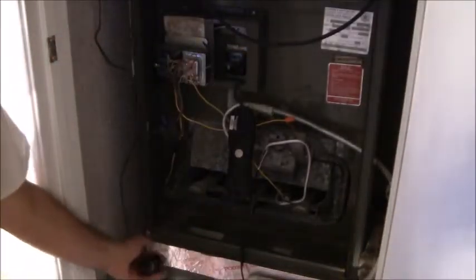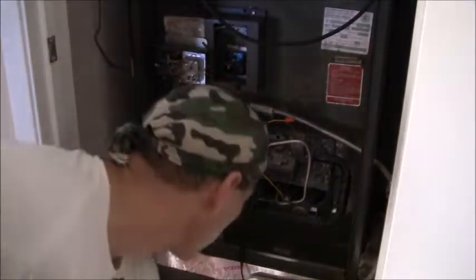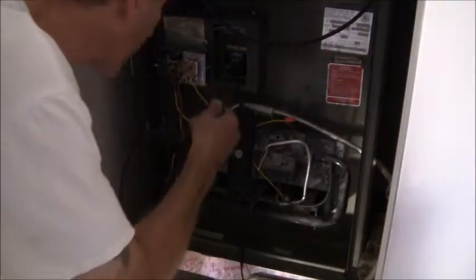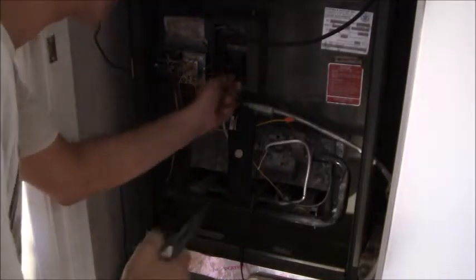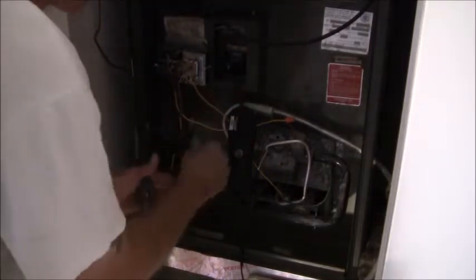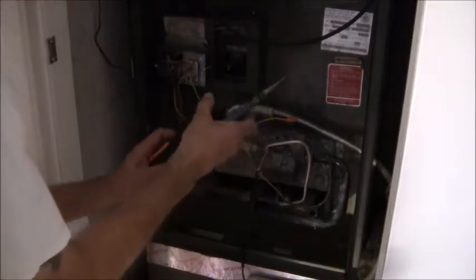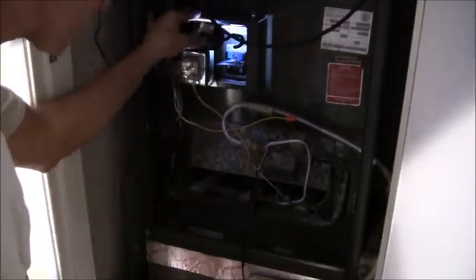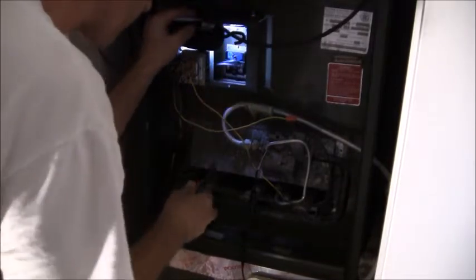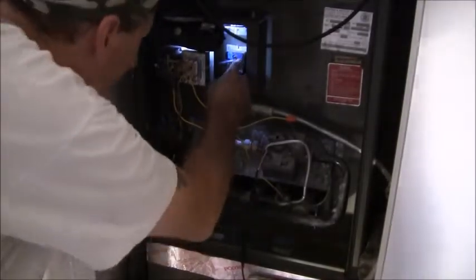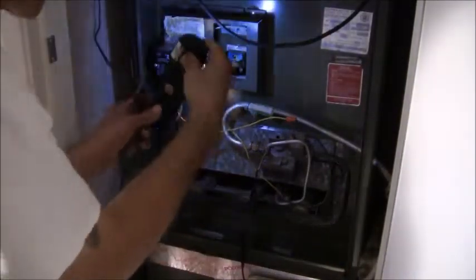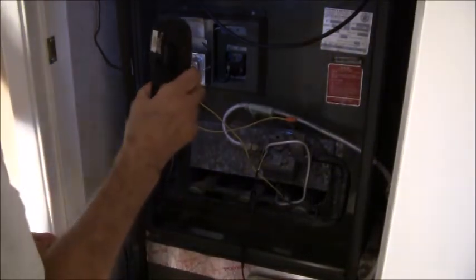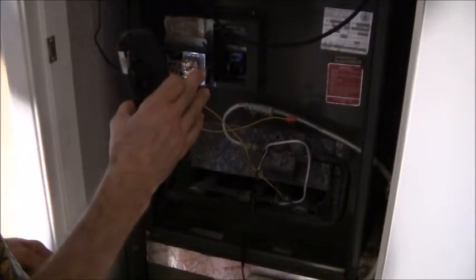Okay, so I disconnected the power, I unplugged the unit. Now I want to pull out my jumper. I've got to figure out which one I want to pull out, the bottom one or the top one. See if I can show you with the light. Put this here, like this. It doesn't matter which one I unplug here, because this is just a switch. So that is good. Thermostat is set at about 95 degrees Fahrenheit. Thermostat is set, I'm fine there. We're totally good. I'm ready to light the burner off.